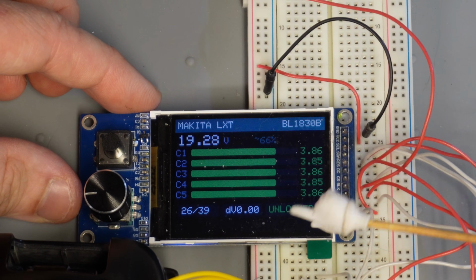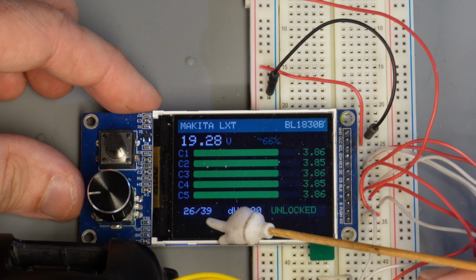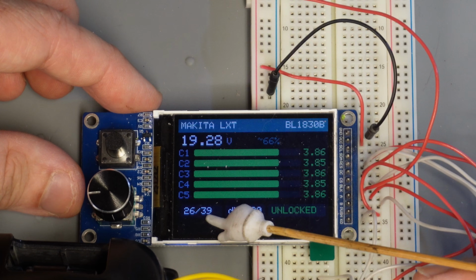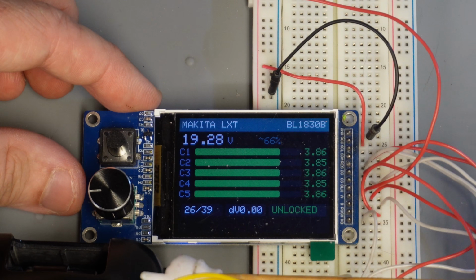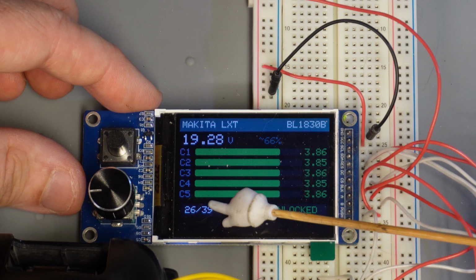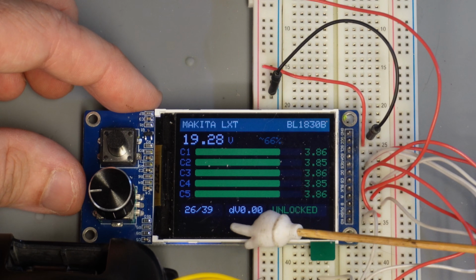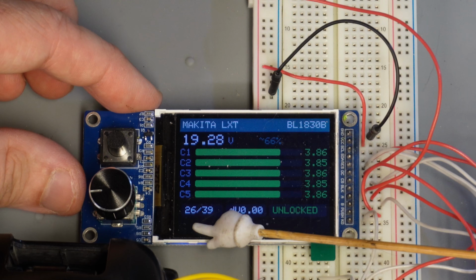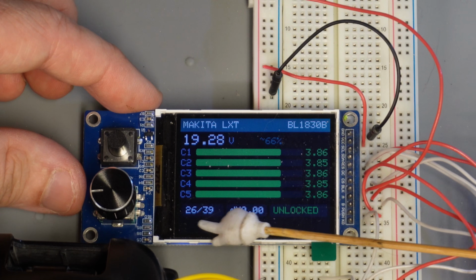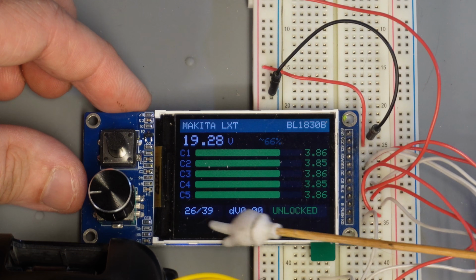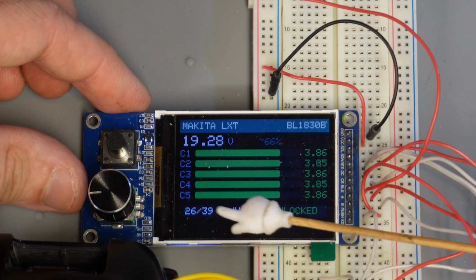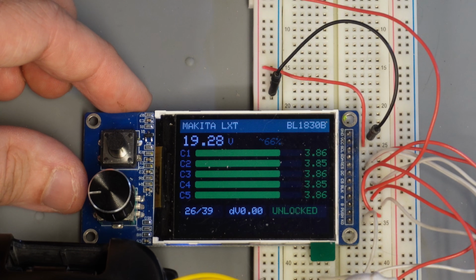Okay, now I see another problem. The gap between those two is too high, we have 26 and 39. One of the things I discovered in the protocol is that there is also a check on the spread in terms of the different measures, and this must be one of those. When you have a 13-degree difference between the two probes, the system will consider that there is an issue. That's why it stopped the charger.